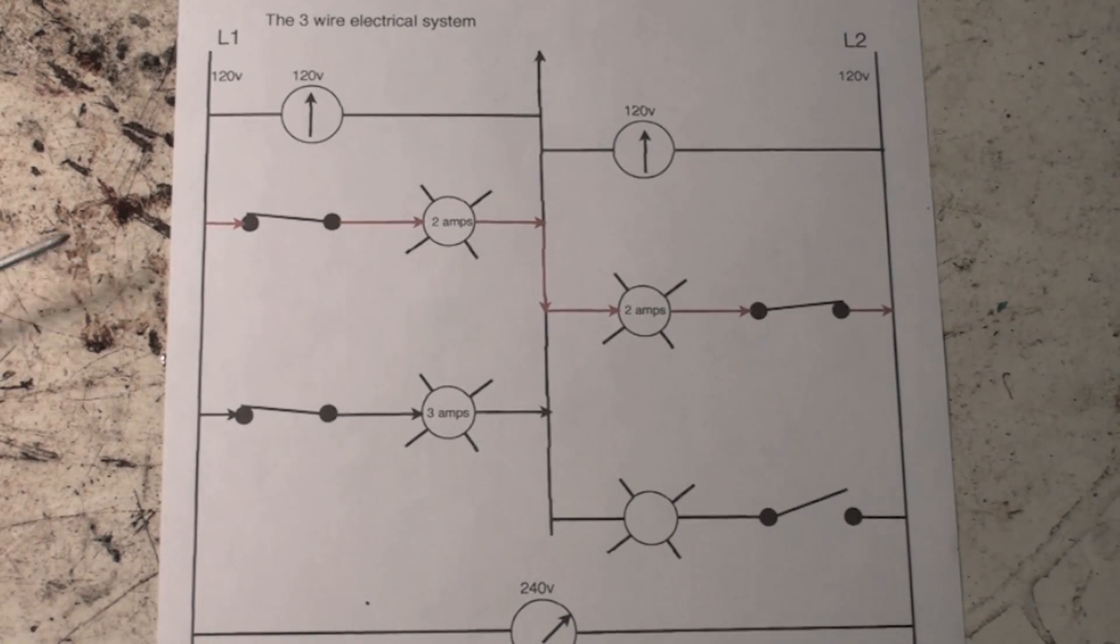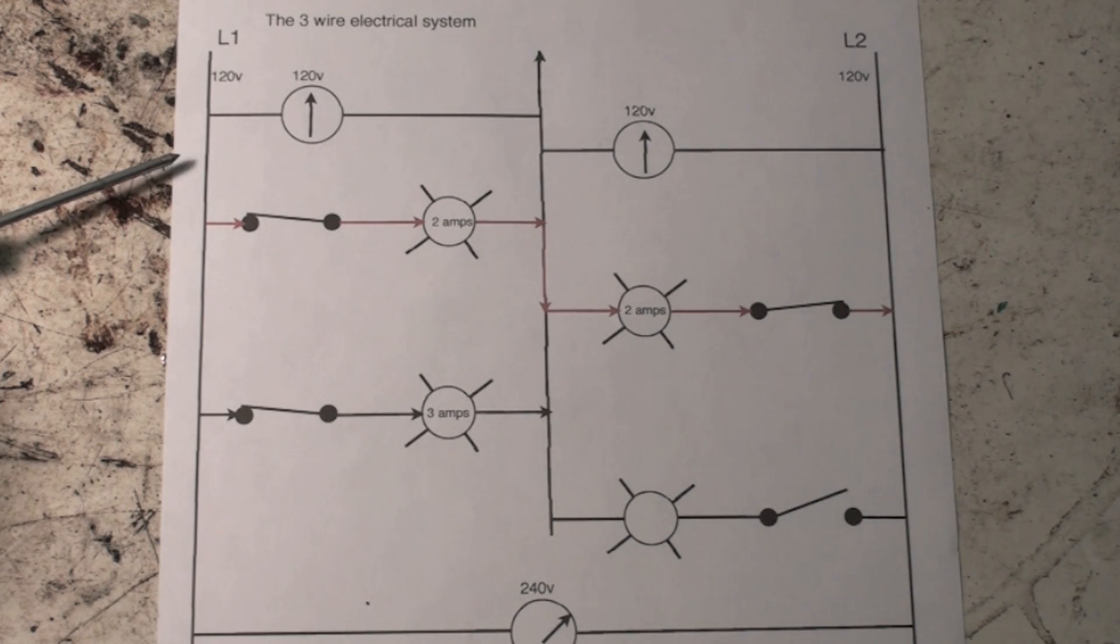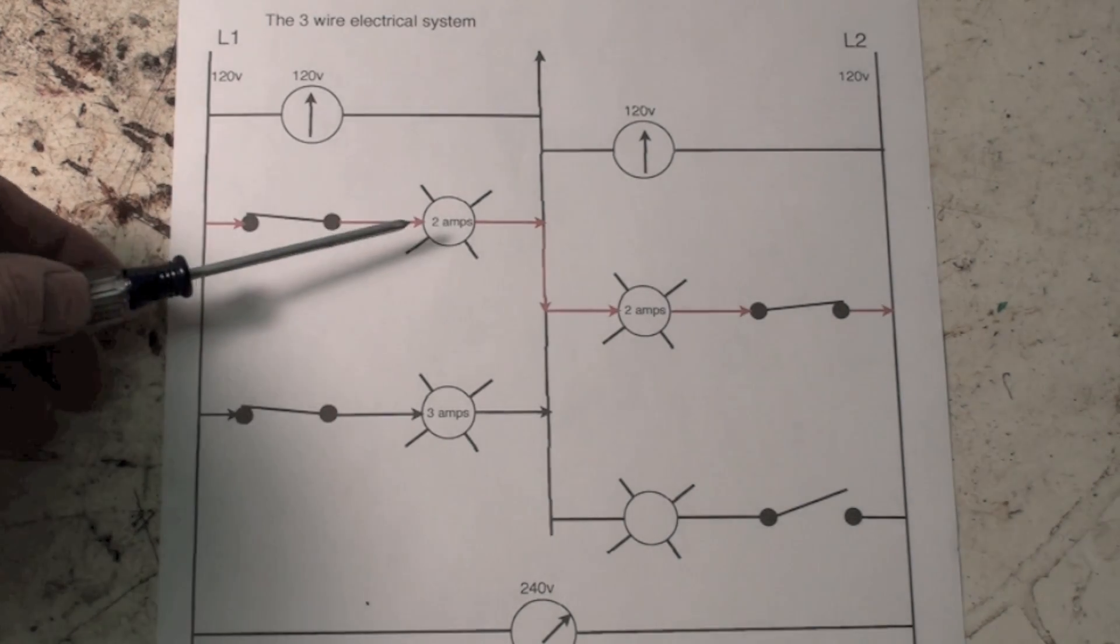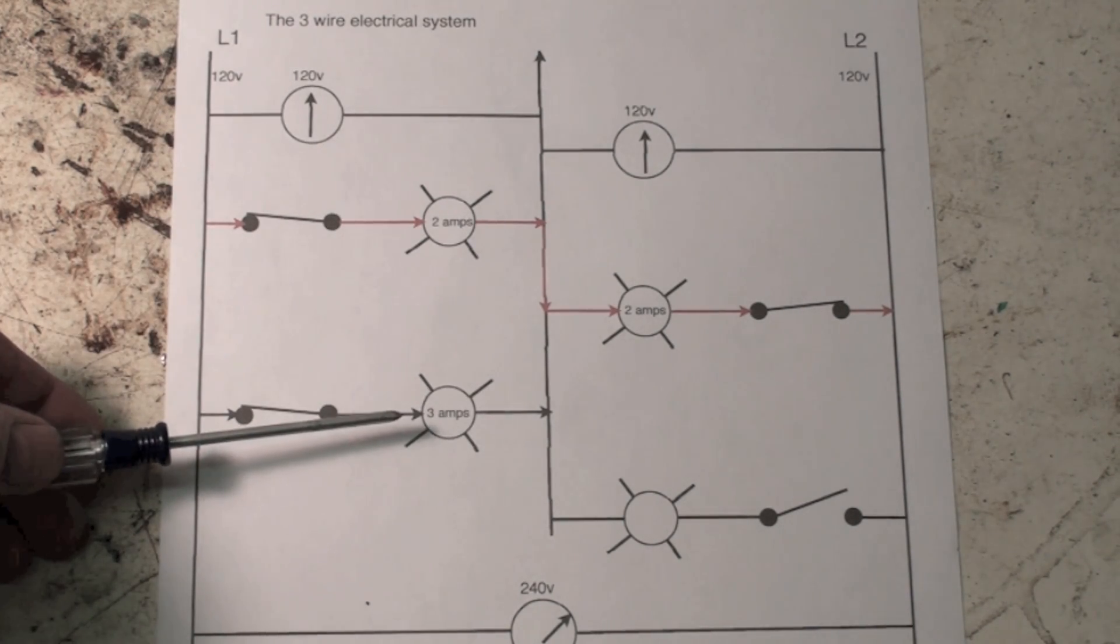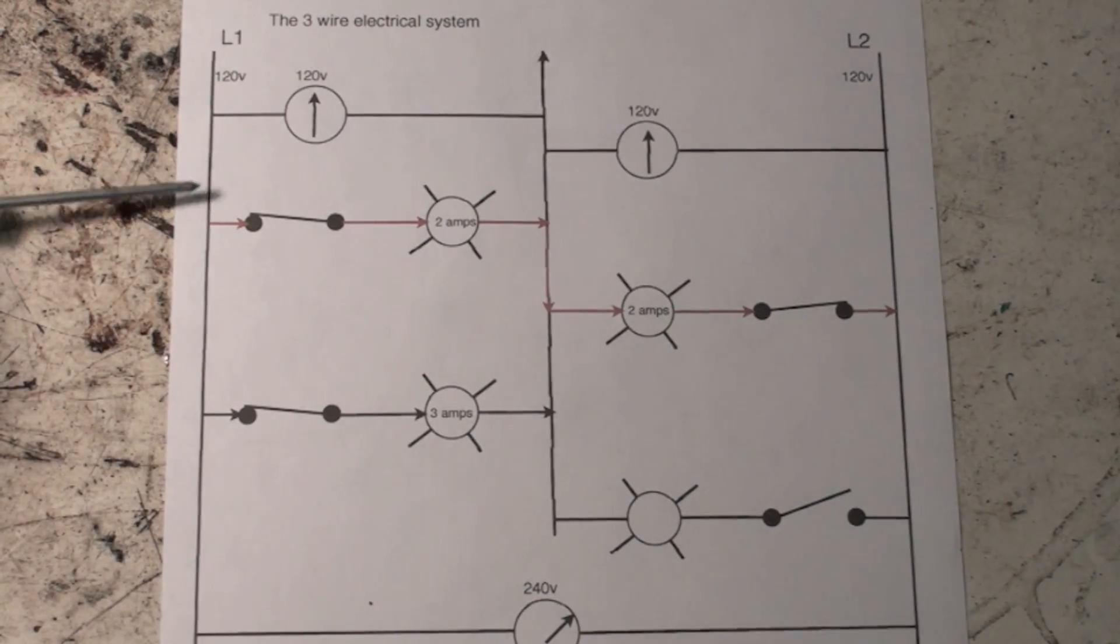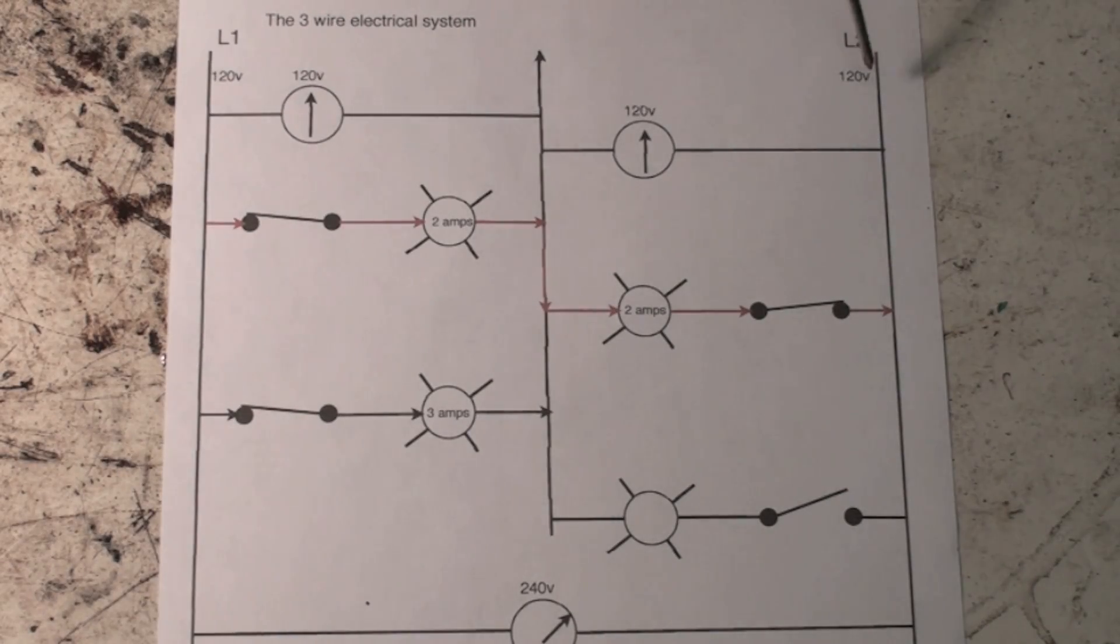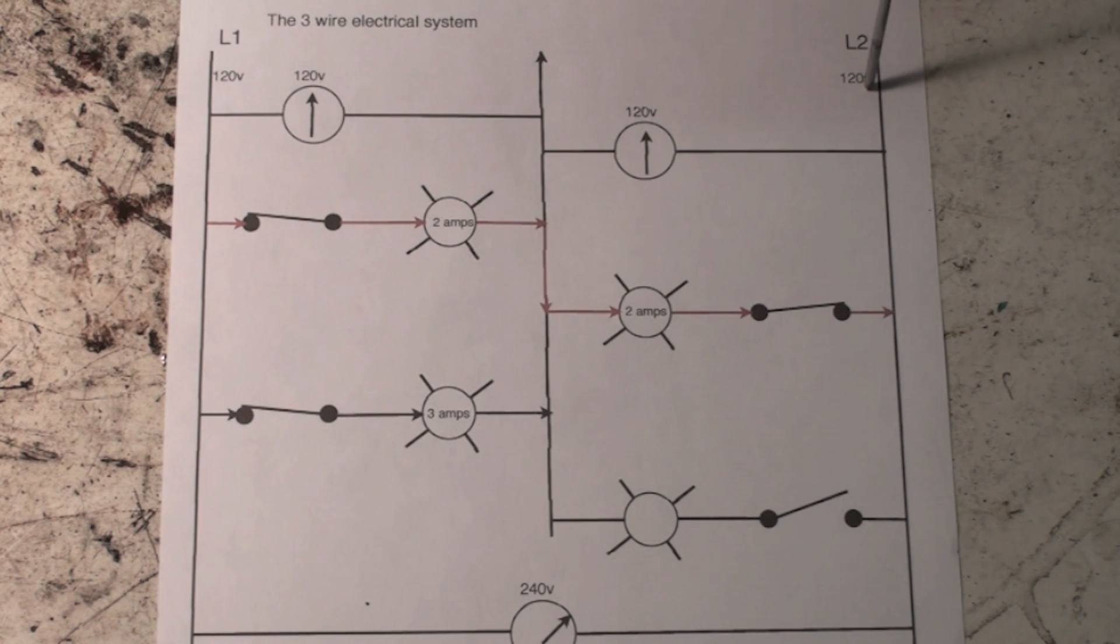I wanted to take a clamp meter and check the amperage draw of this line here. If I put my clamp meter around this wire here, it would read 2 amps plus 3 amps because that's what's going through this line—power coming through here, power coming through there. If I were to clamp this line right here, it would read 2 amps because there's only 2 amps going through this side.